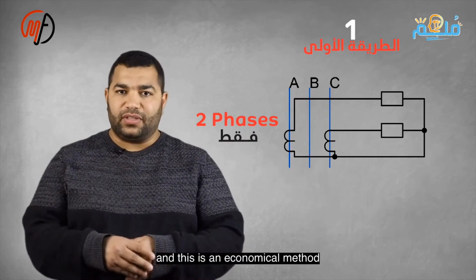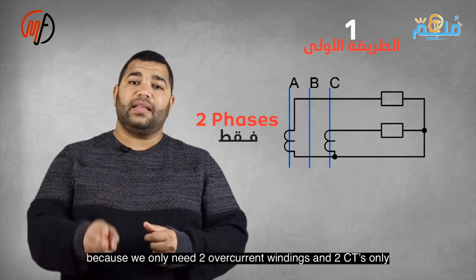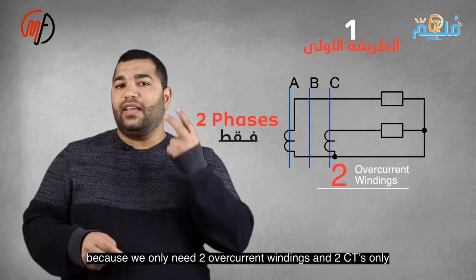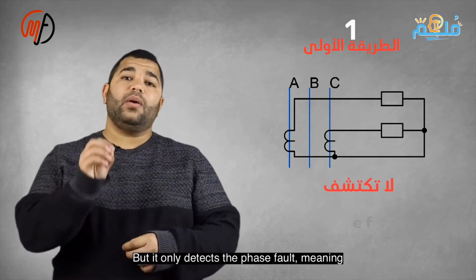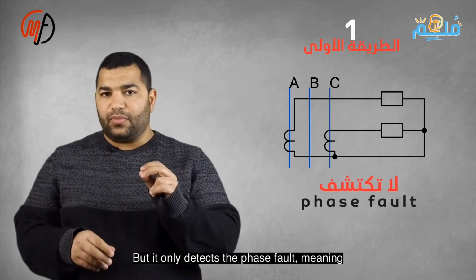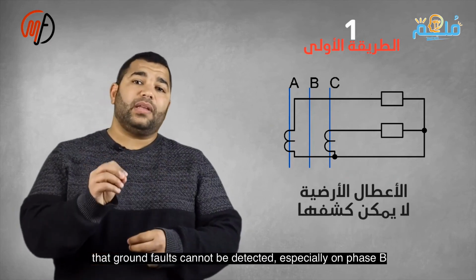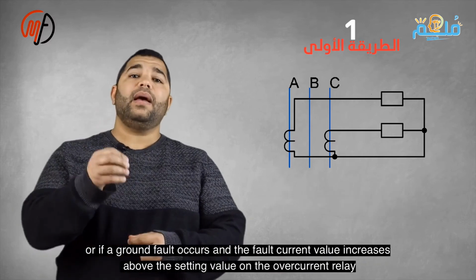This is an economical method. Only two overcurrent windings and two CTs are needed, but it can only detect phase faults, meaning ground faults are undetectable. An earth fault relay, requiring a third CT, can be added to detect ground faults.